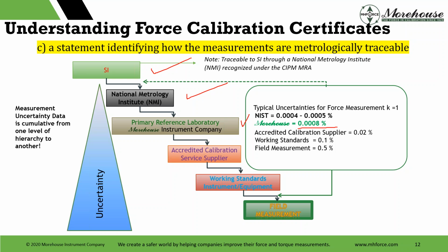And our traceability is to SI units, and it's validated by NIST calibrations on our several deadweight force machines, and we provide our additional metrologically traceable force transducer calibrations. NIST does the calibration for our force standards, our load cells, up to 1 million pounds and up to 2.25 million, or 4.4 meganewtons to 10 meganewtons. NIST does the calibrations on those load cells, and the one where we are going to 10 meganewton, NIST calibrates 3 load cells close to 1 million pounds to get there.